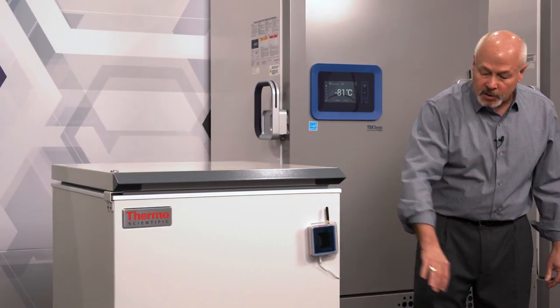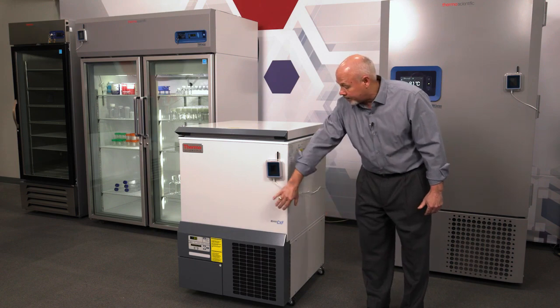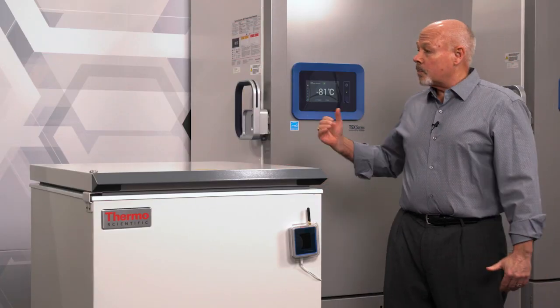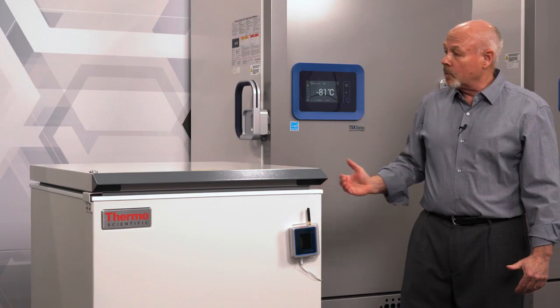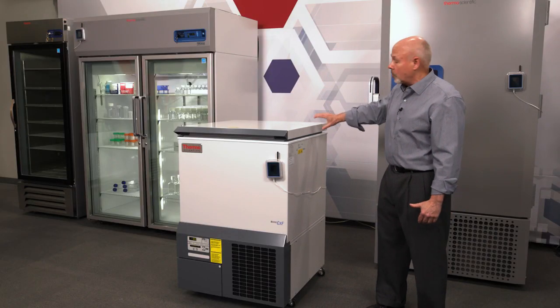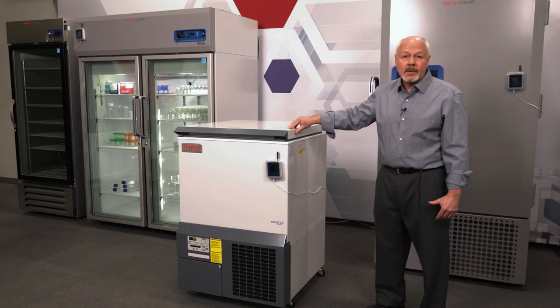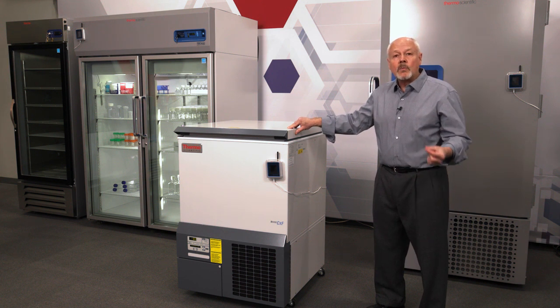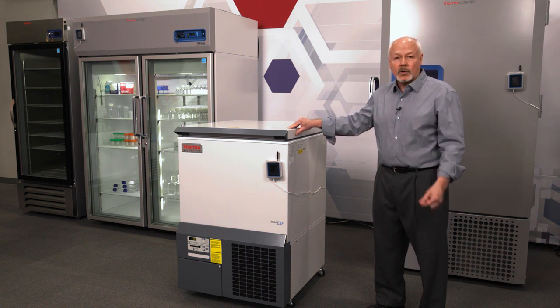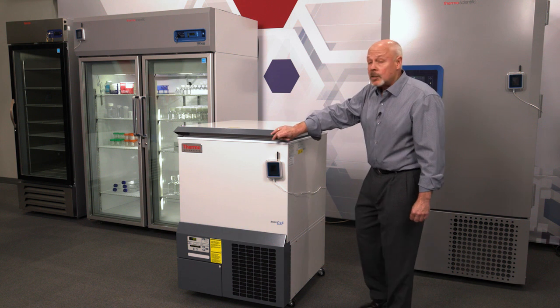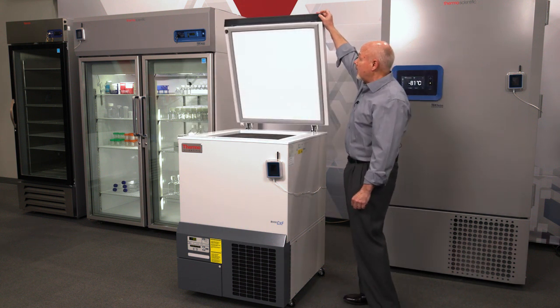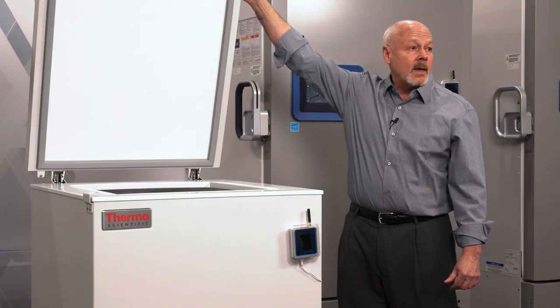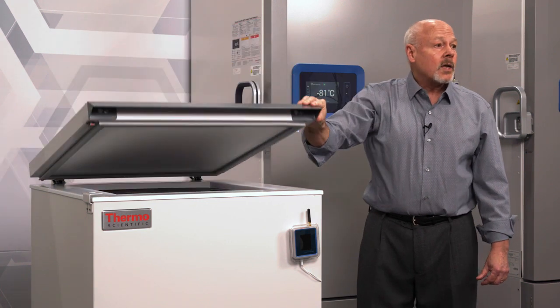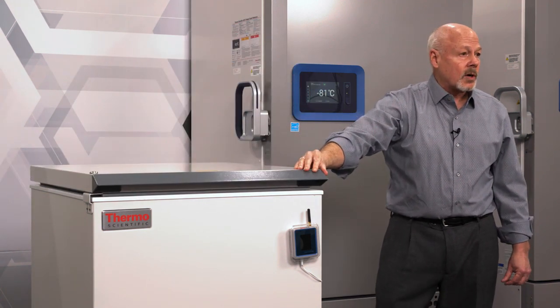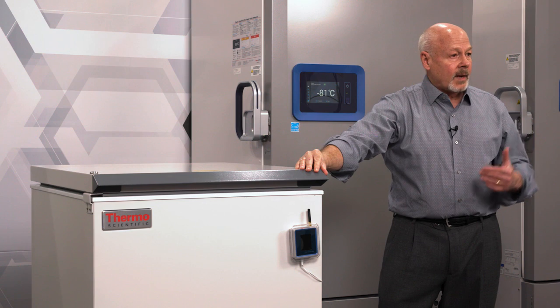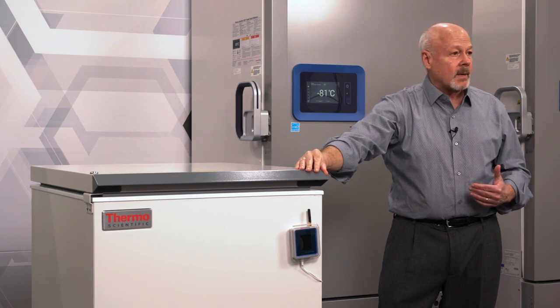You want to make sure you're installing it on a level floor. You want space around the unit. So it's really important to have ventilation around the unit on the sides and in the back. It should be installed in a room that's between 18 C and 32 degrees C. Ensure there's room also for the lid so that there's no obstruction. And then from an electrical standpoint, you plug it into a 115 volt circuit that's dedicated. Don't have any other products that are installed on that same circuit.